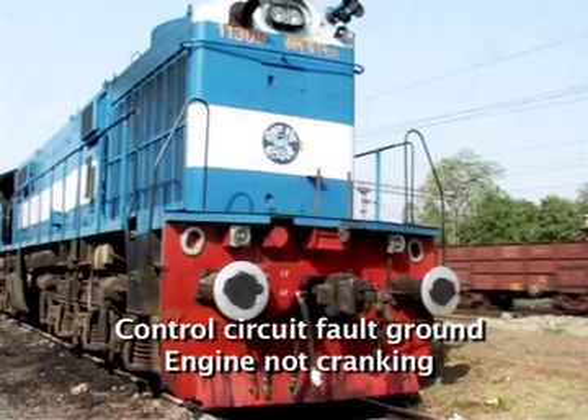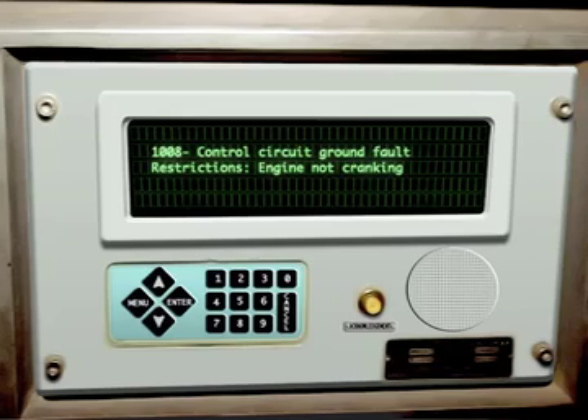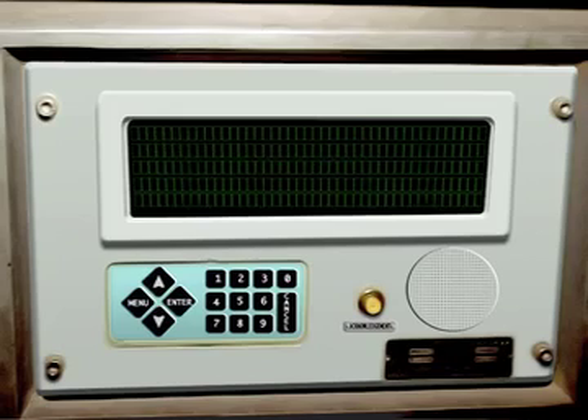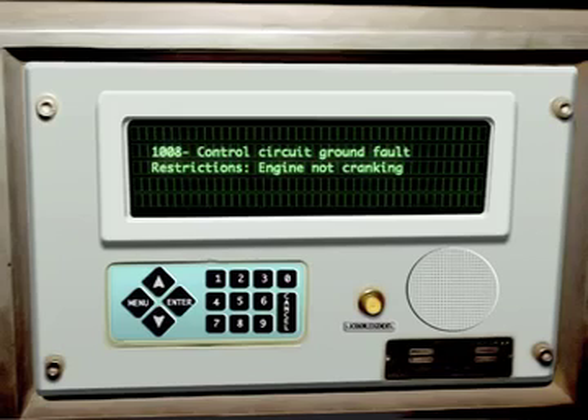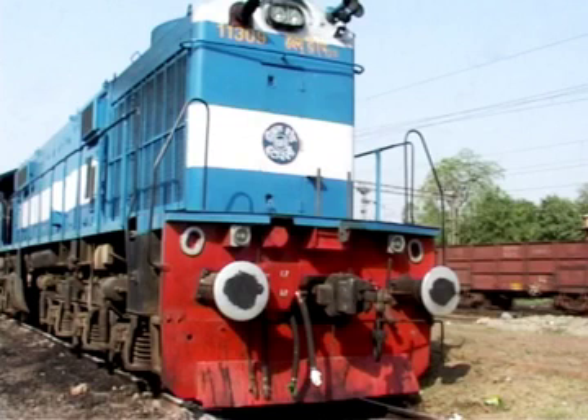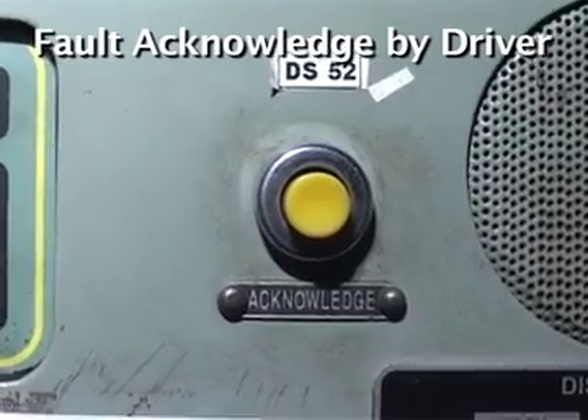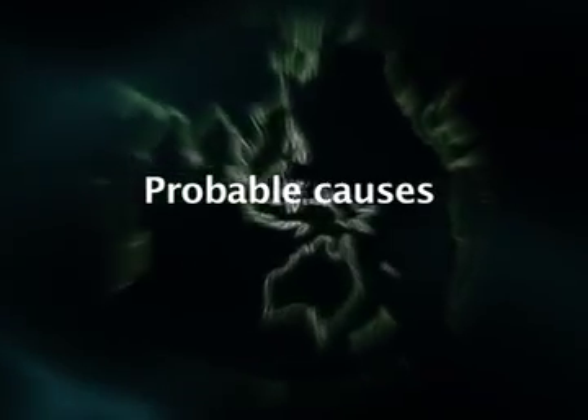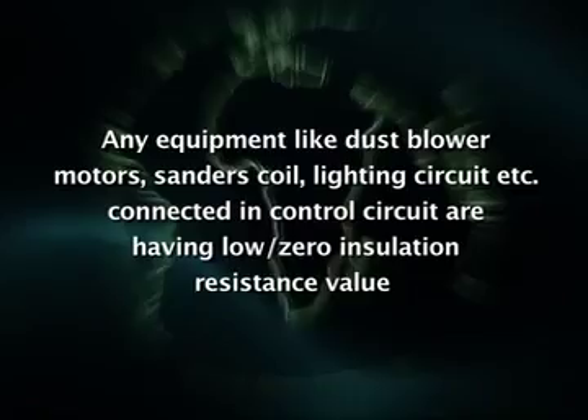Control circuit starting ground fault coming and engine not cranking. Fault message coming. Control circuit ground fault. Message code 1008. Restriction: engine not cranking. Alarm bell ringing continuously with buzzer for 30 seconds. Driver acknowledging fault. Probable causes: any control circuit wiring is grounded.